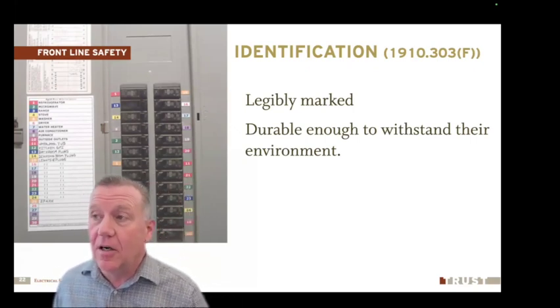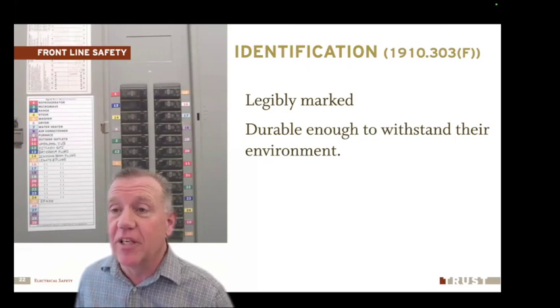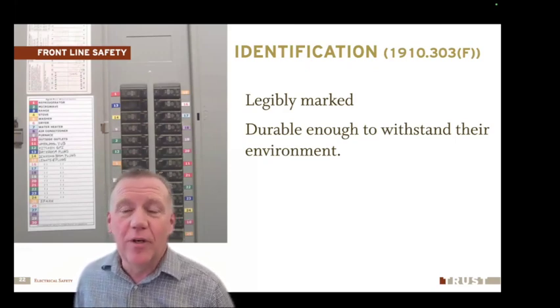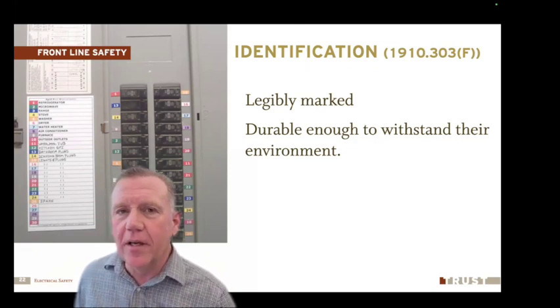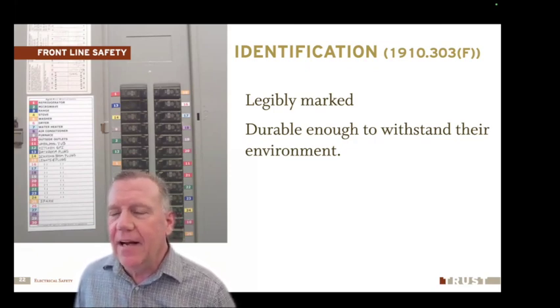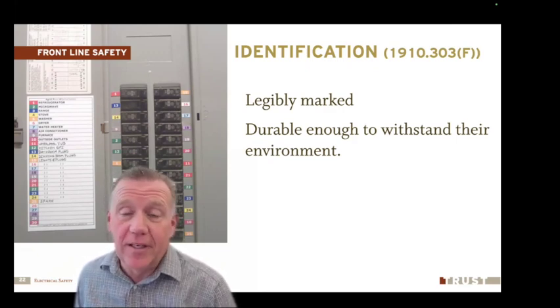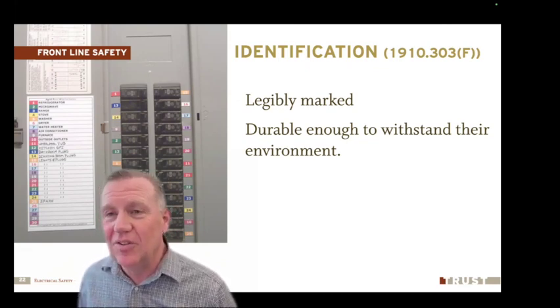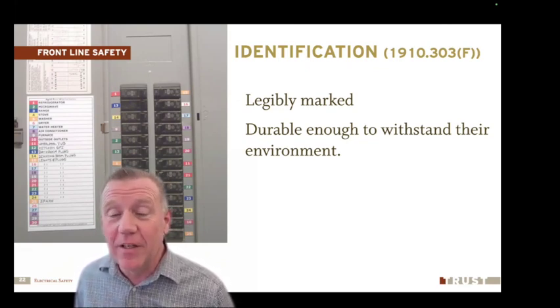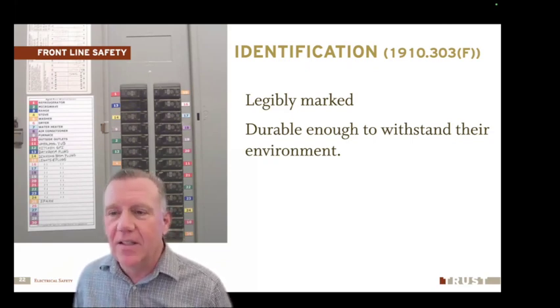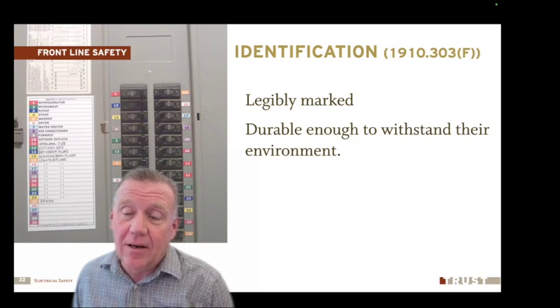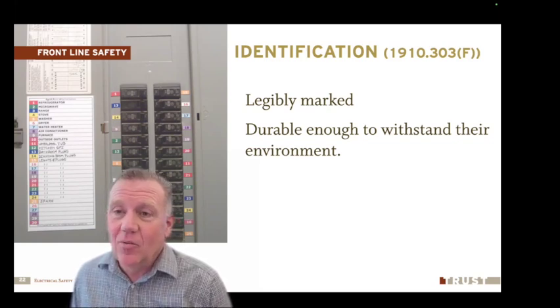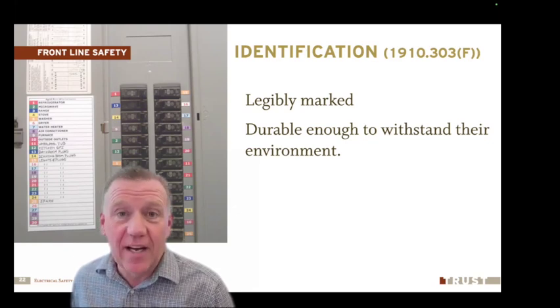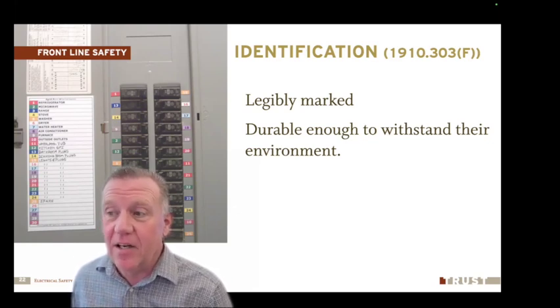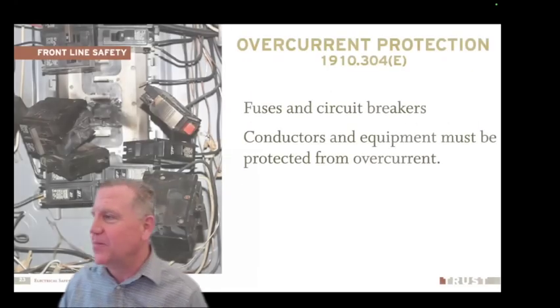All of our overcurrent protection, or circuit breakers, need to be legibly marked. We need to identify where those circuits go and what they serve. What if I have a breaker in that panel that isn't used - it's a spare? You should still go to the list where we're labeling what they serve and put down 'spare.' That's the OSHA standard, and that's what they can cite you on. But more important than that, I don't want to be guessing which breaker serves what, because that can cause problems, fires, and lots of other challenges.